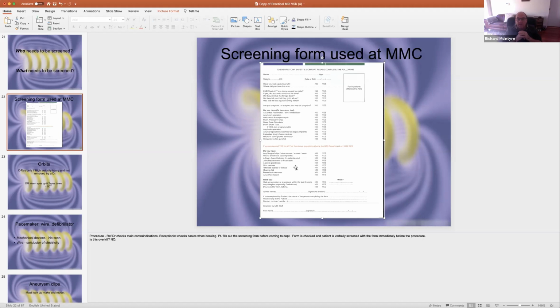And then when the patient gets to the centre, they'll fill in this form that states that they do not have a Swan-Ganz catheter. They don't have any surgical clips, wire, sutures, screws, mesh in their body. They don't have a pacemaker or a heart operation, and they'll sign this form, okay? We'll check it verbally with them, and we'll go through all the main things verbally to make sure that's all correct. We'll sign it as well, and then we'll do the scan, okay? If the patient hasn't filled out and signed the form, we will not do the scan. No MRI department will do the scan if that form has not been completed and it has not been verbally assessed with the radiographer. It's too important, okay?